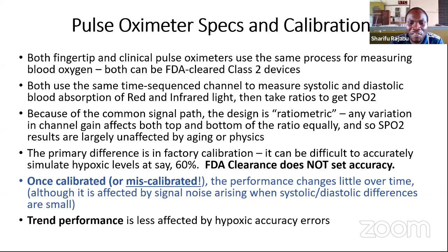So here's what I was saying. We have diagnostic with monitoring, where are the application of specification and diagnostic. So those pulse oximeters that are not accurate, those fingertip pulse oximeters, they tend to be inaccurate on the lower range of hypoxia level. They should be used by those patients that are self-isolated, that don't need a critical care condition.